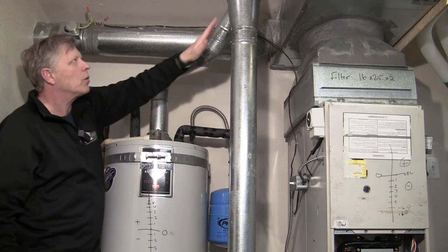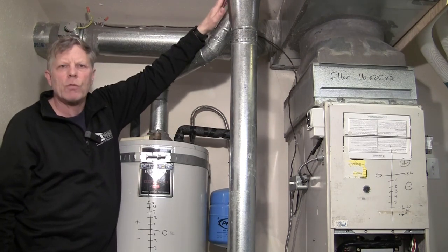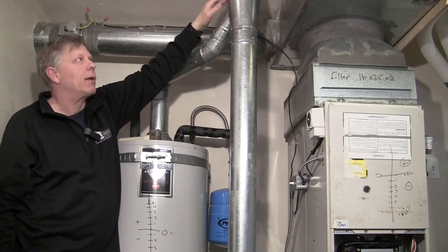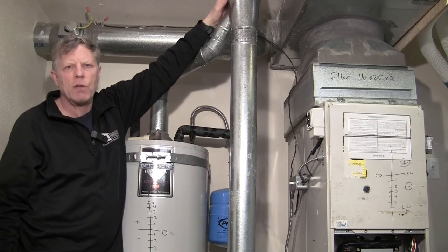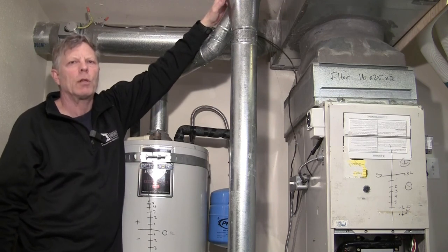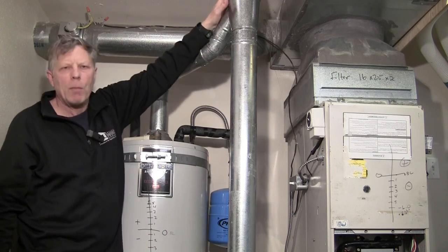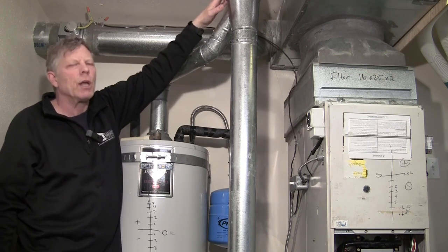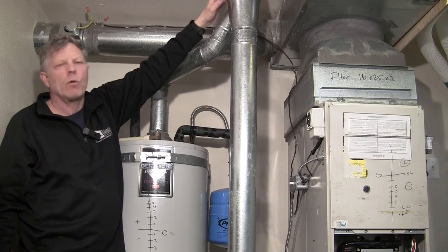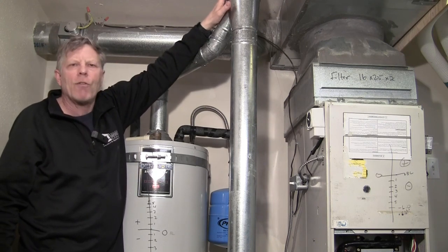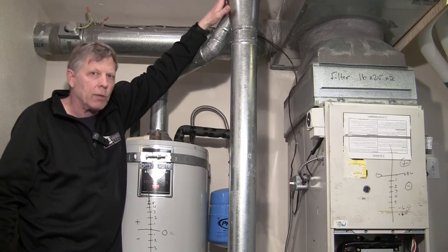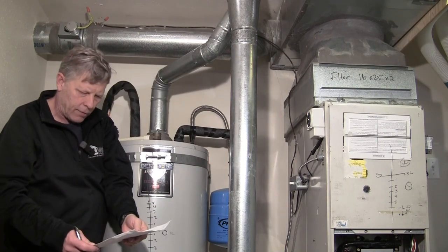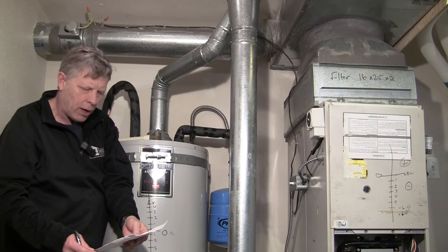The next thing we do is we look at where this chimney goes through the attic. Check and make sure it's not too close to the framing. This portion of the chimney is B vent. It has a 1-inch minimum clearance to combustibles, so we want to make sure it has clearance to framing up there of more than 1 inch. And then of course we'd also want to check to see how far away any insulation was from the chimney. So that should take care of line 4 on our combustion sheet.